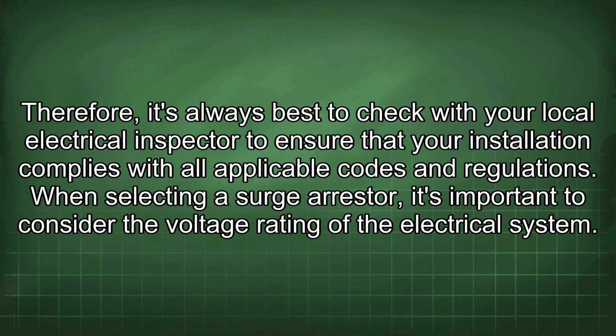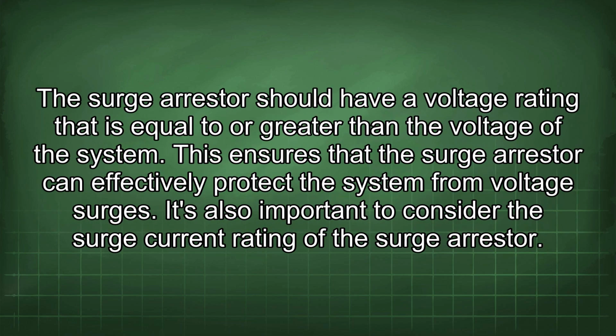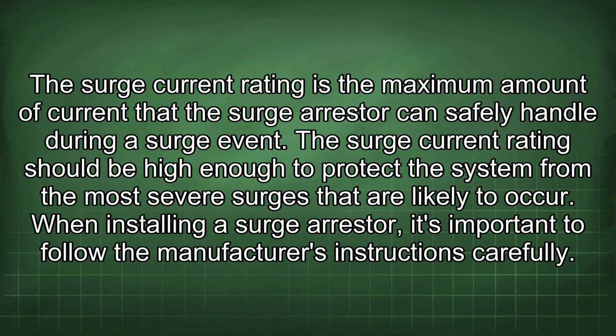codes and regulations. When selecting a surge arrestor, it's important to consider the voltage rating of the electrical system. The surge arrestor should have a voltage rating that is equal to or greater than the voltage of the system. This ensures that the surge arrestor can effectively protect the system from voltage surges. It's also important to consider the surge current rating of the surge arrestor. The surge current rating is the maximum amount of current that the surge arrestor can safely handle during a surge event.